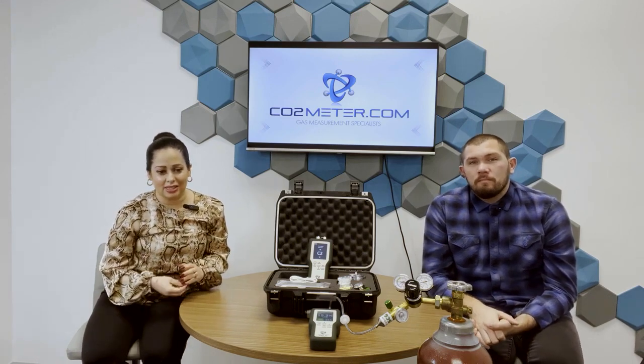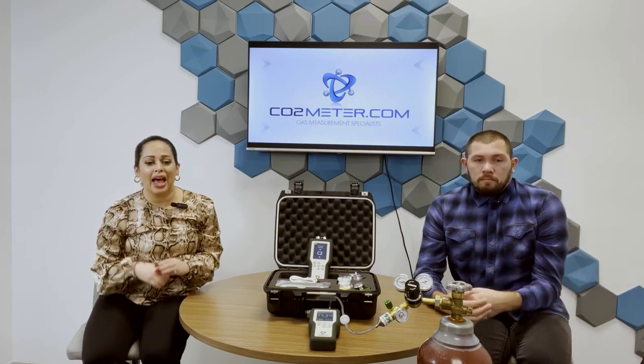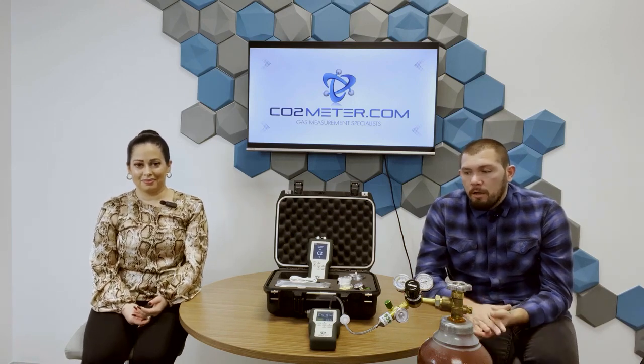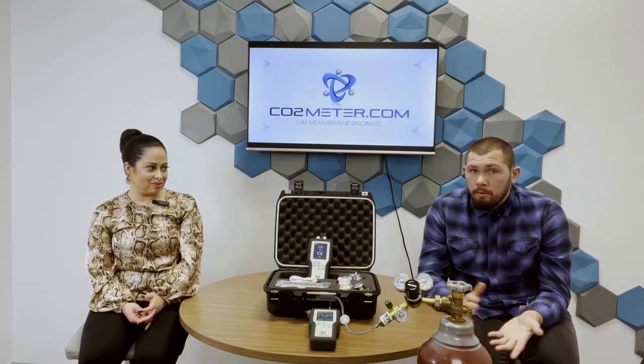Let's talk about one of the key features of this device. We have a question asking, what do I do if the device tells me my gas is out of spec? The point of this device is to verify the gas in front of you. So if you get that red stop, first step, I would suggest turning off the device, restarting it, allowing those sensors to reinitialize, and take your measurement again. User error is sometimes a possibility, so you want to make sure you're 100% right that the gas is not within spec.